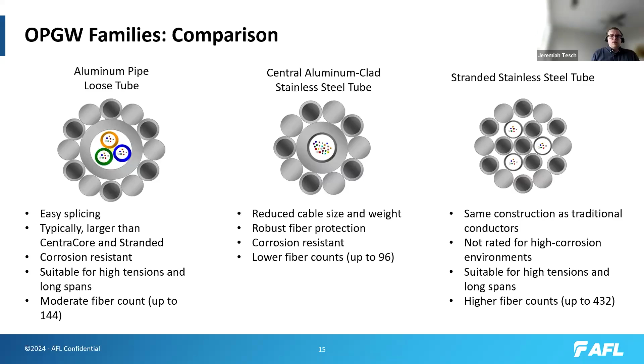All right, so hopefully that makes sense. I know that was a lot of information. Key properties for OPGW: a lot like conductors, you will have tension ratings, but since we have fiber, there's one additional tension rating. Typically with conductors, you use the rated breaking strength, which is the rating at which the cable is actually rated to fail.